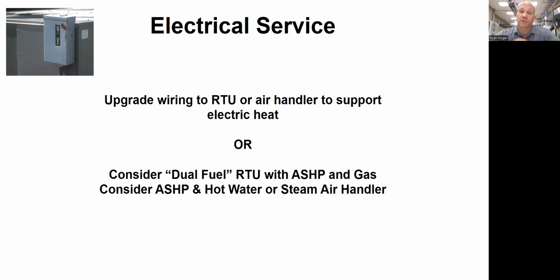So that's where the dual fuel comes in nicely, because you can put a lot of hours on the heat pump, like we talked about last week. 80, 85, 90% of your heating run hours could go on the heat pump. And when it gets too cold and the heat pump can't keep up, because I size it for cooling, not for heating, then I turn it off and I switch over to the gas-fired system that I already own, right? So you could do that. It's easier to do that on a split system than on a rooftop unit.